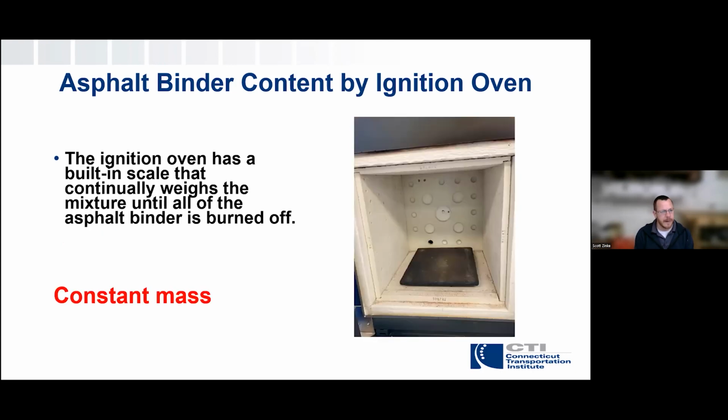All right. And so what you see here, this is looking inside the ignition chamber itself. It's thermally isolated. What you're looking at, those white walls, both in the back and on the top and on the sides, that's the thermal isolation. Those are insulated walls. And on the bottom, what you see is a platform. And that platform goes down to a scale that sits on top of the computer in the bottom of this machine. And that also has to be thermally isolated, obviously, because if it wasn't, we would simply burn the whole unit up. And we've got to make sure that doesn't happen.